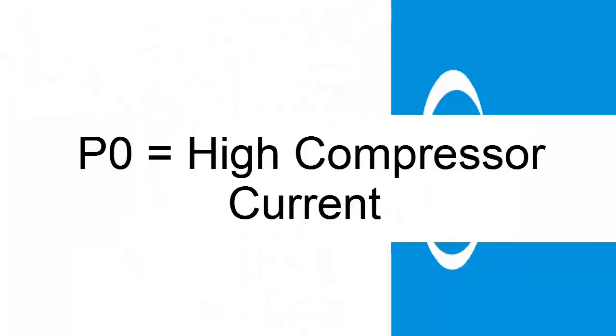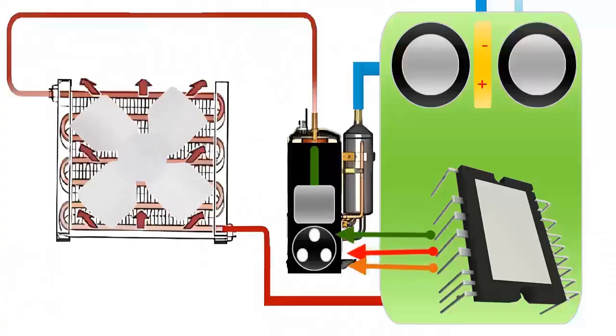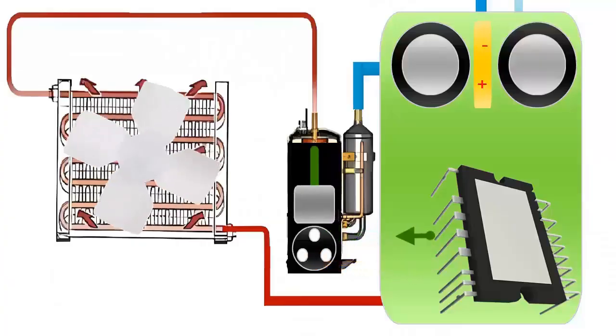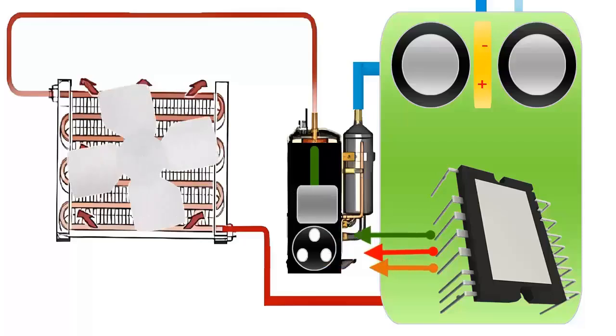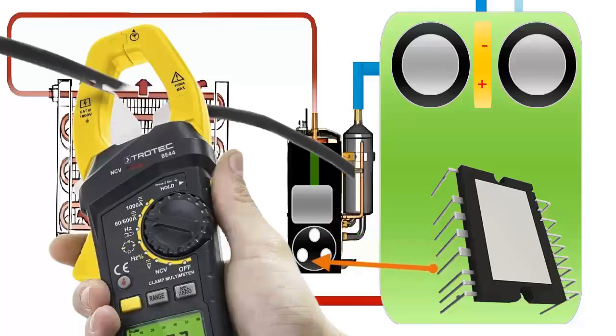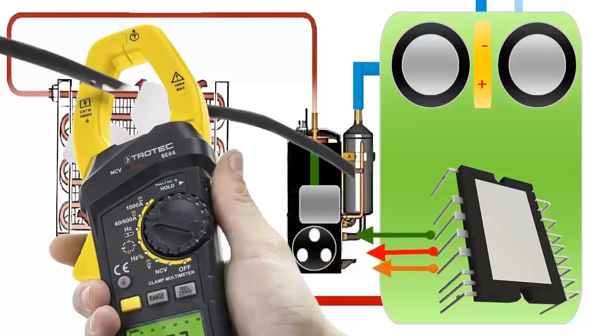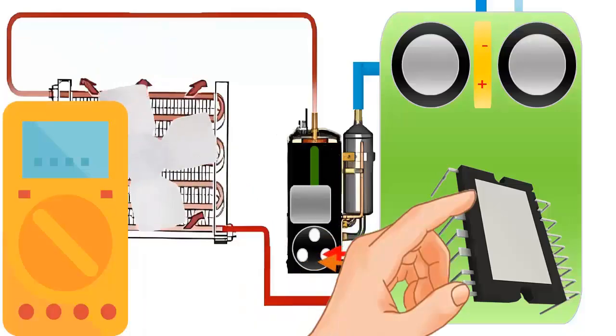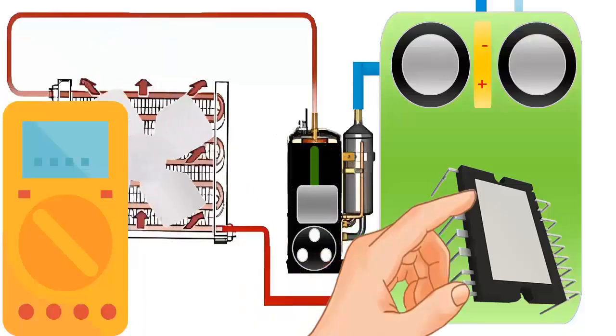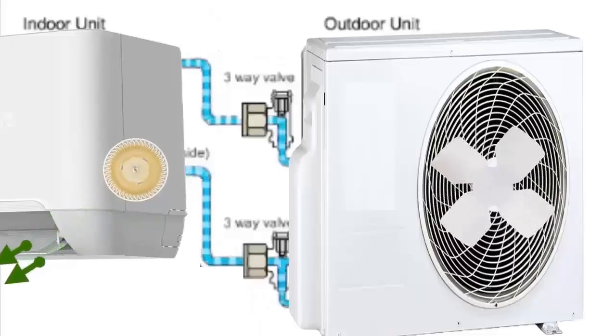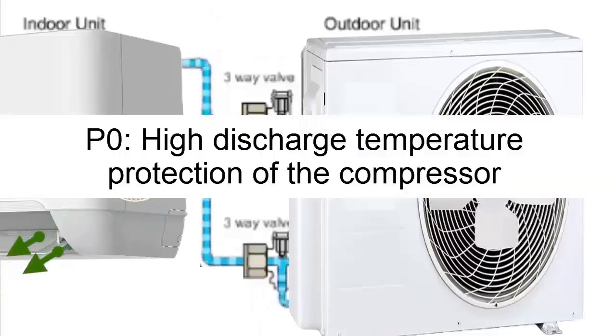Code P0 generally indicates high current protection in one of the IGBT transistors, likely due to a failure in the inverter module or an internal short circuit. Recommendations: A. Inspect the electrical wiring that powers the compressor. B. With a multimeter, check the inverter module for possible short circuits, as we will show at the end of the video.